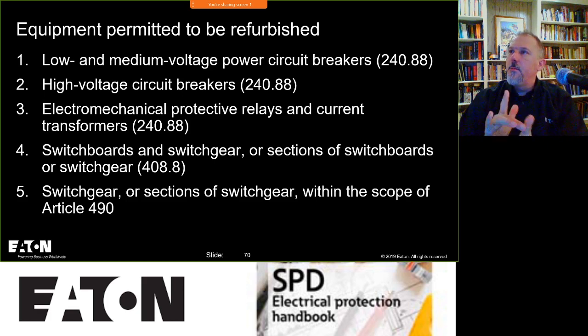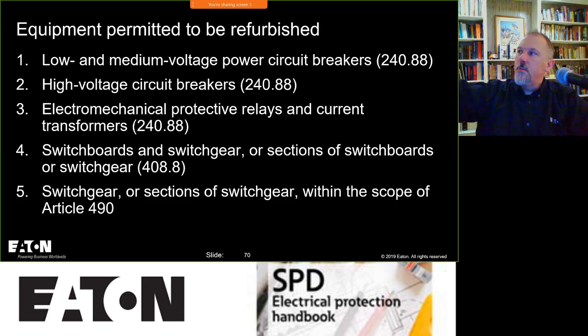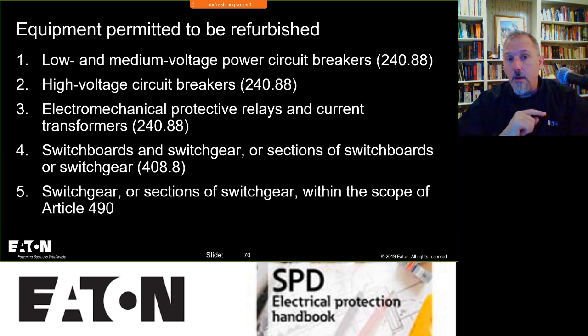Equipment permitted to be refurbished. Now this stuff is, we gotta remember, a lot of people say, well, I looked in 240.88 and it says I can refurbish, recondition power breakers. I can refurbish and recondition high voltage breakers. I can refurbish and recondition switchboards and switch gear, but there's nothing in here that says I can refurbish and recondition my motor.